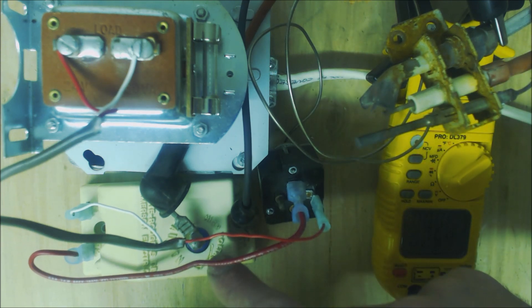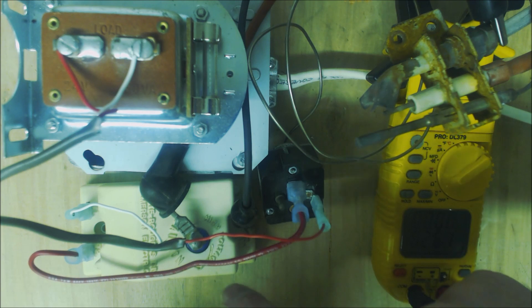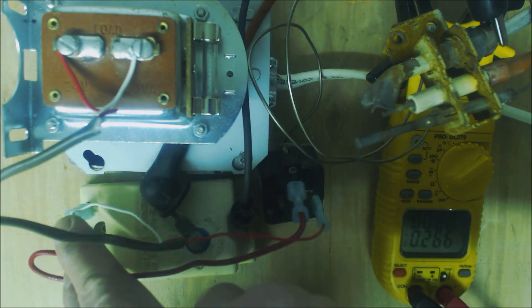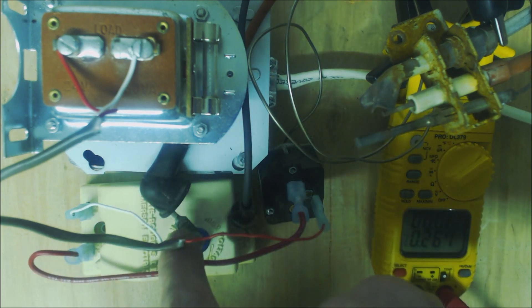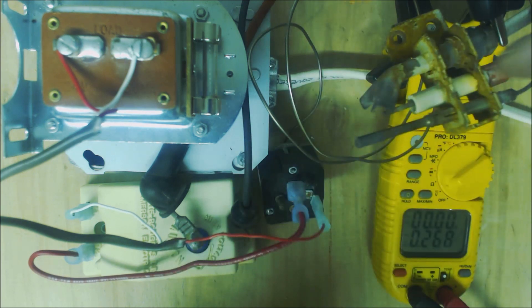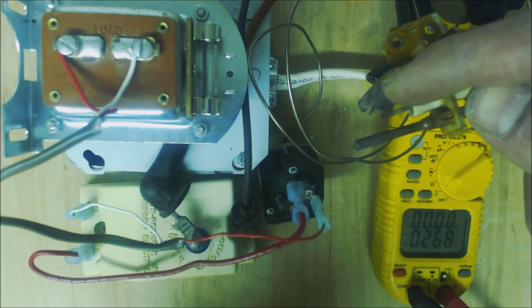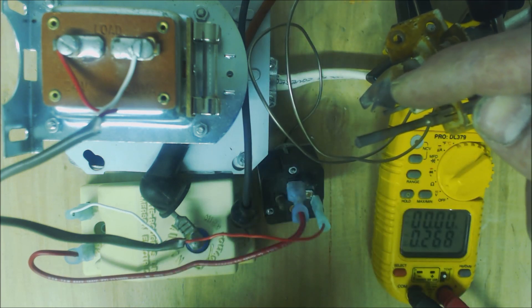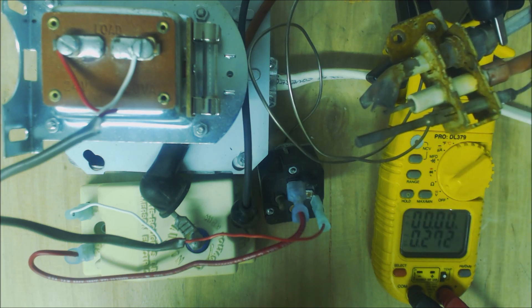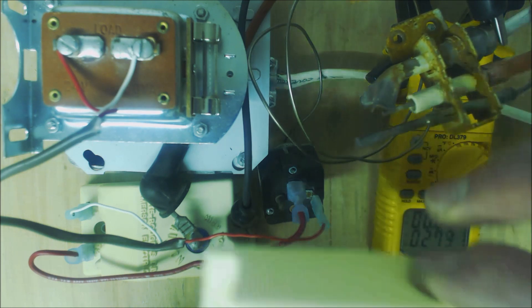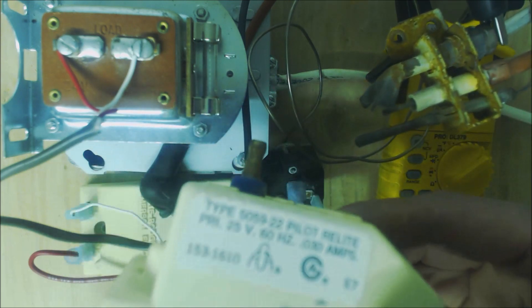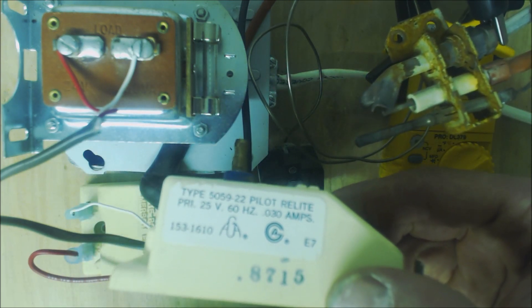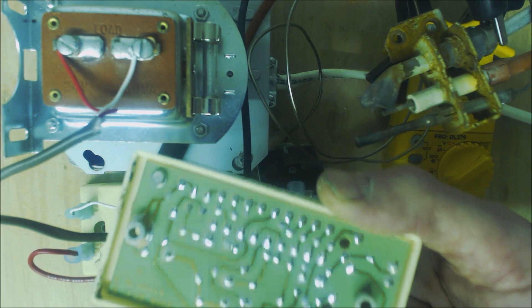This is a spark relight. Its job is to have 24 volts come in and 6,000 volts come out, coming over to the spark rod and jumping across to the pilot housing to ignite the gas. Here's an up-close view - it's high voltage, low amperage.